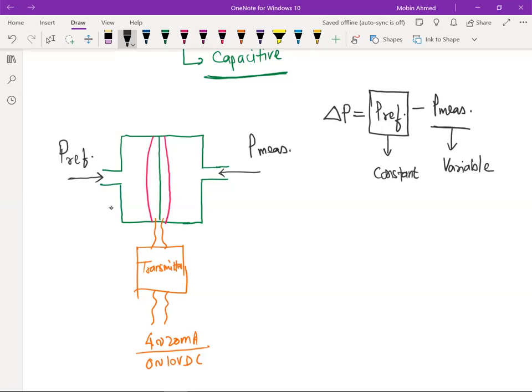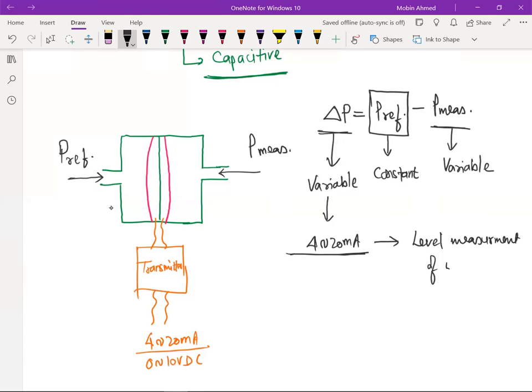So if it is going to vary, of course, the output, that is the delta P, is also going to vary. It is also a variable. So this variable is why we are going to get the output of 4 to 20 milliampere. The difference between the pressure, if it is a variable, can be converted into the current 4 to 20 milliampere. And we know how much the pressure is now, so at what level. So this can be used as a level measurement of water.